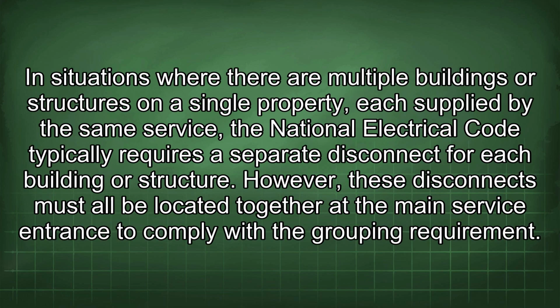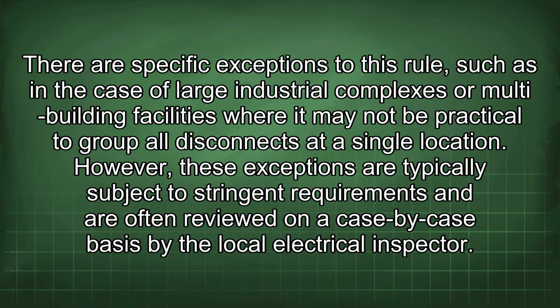In situations where there are multiple buildings or structures on a single property, each supplied by the same service, the National Electrical Code typically requires a separate disconnect for each building or structure. However, these disconnects must all be located together at the main service entrance to comply with the grouping requirement. There are specific exceptions to this rule, such as in the case of large industrial complexes or multi-building facilities where it may not be practical to group all disconnects at a single location. However, these exceptions are typically subject to stringent requirements and are often reviewed on a case-by-case basis by the local electrical inspector.